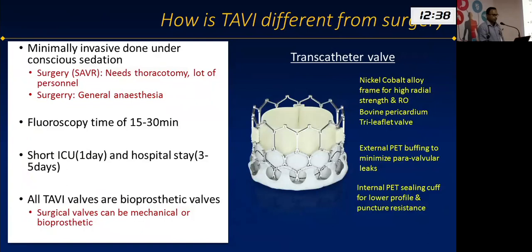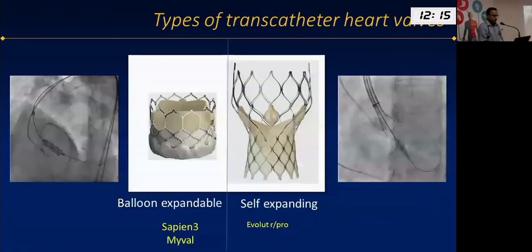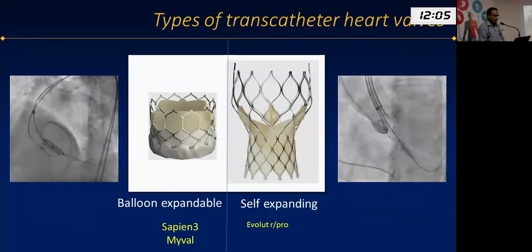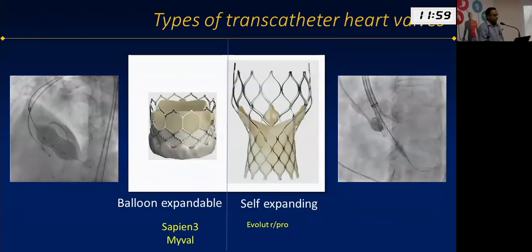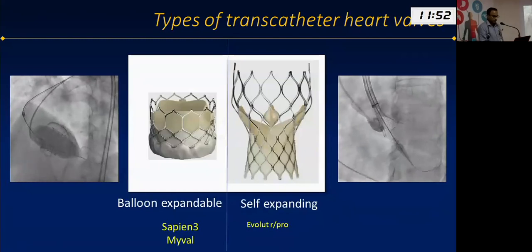All TAVI valves are bioprosthetic — tissue valves — which means they don't require long-term anticoagulation. A transcatheter valve essentially has three parts: a metallic frame, tissue valve leaflets usually made of bovine or porcine pericardium, and an external and internal sealing skirt to reduce paravalvular leaks. These valves are classified as either balloon-expandable or self-expanding. A balloon-expandable valve is crimped onto a balloon and deployed by inflation; a self-expanding valve is constrained within a catheter and deployed by retracting the catheter.